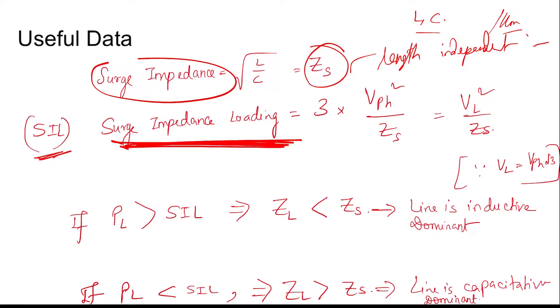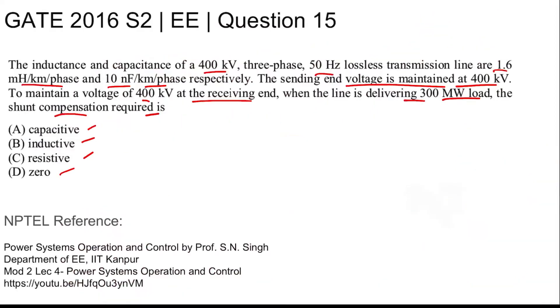If you see that the surge impedance loading (SIL) is less than the loading on the line (P load), that implies ZL is less than Zs, which implies that the line is inductive dominant. So if the surge impedance is more than the loading impedance on the line, then the line is inductive dominant. And if the loading is less, then the load impedance is more than the surge impedance, and hence the line is capacitive dominant.